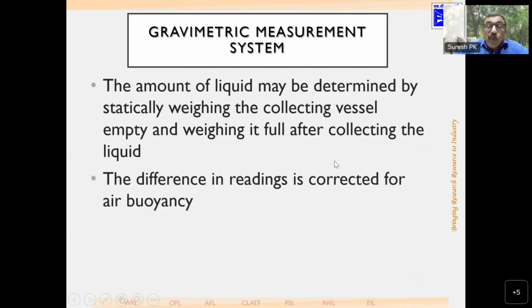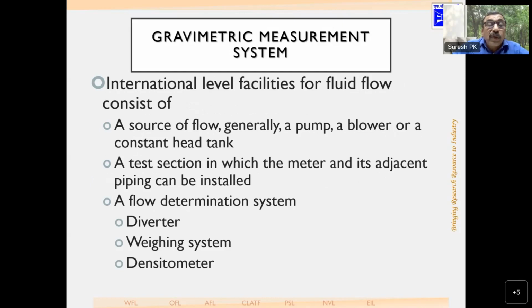The amount of liquid may be determined statically by weighing the collecting vessel empty and weighing it full. That is, before the start of the flow, you make the measurement of the vessel, and then after diversion, you weigh it full after collecting the liquid. The difference in readings is corrected for air buoyancy, and then it is used for calculation.